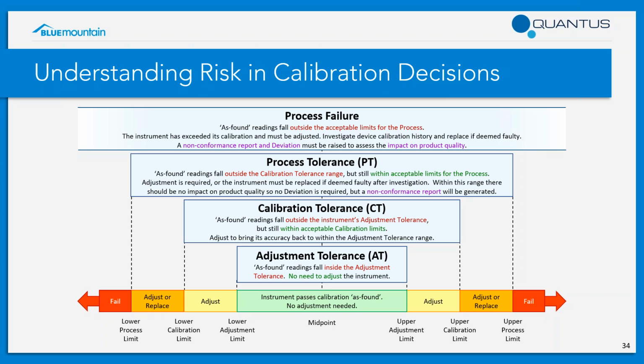It's also a good idea to investigate the device calibration history and replace it if it's deemed faulty, or if we find that it requires repeated adjustments or repeatedly falls outside of this tolerance. In this case, a non-conformance report and a deviation must be raised to assess the impact on product quality. So hopefully that talks you through the different levels and gives you some understanding of how they relate one to another.